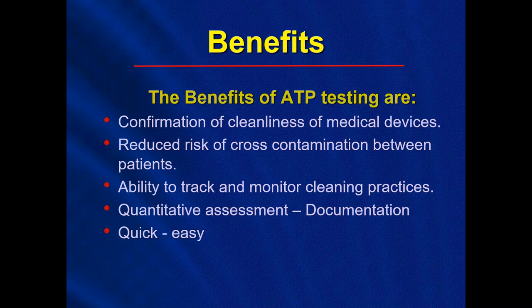Maybe you have John and Jane who are cleaning the scopes, and you notice that for some reason, John's having more positive ATP tests than Jane. Maybe that's somebody who needs to be re-educated. Again, auditing is also very important in scope cleaning and verification. Also with ATP, it's a quantitative assessment. You get a number used for documentation, and above all, it's a quick and easy test. Unlike cultures, which could take 2 or 3 days, an ATP test takes as little as 15 seconds to get a result.